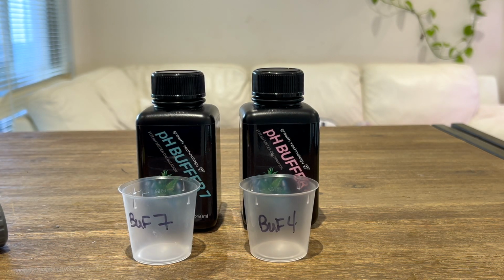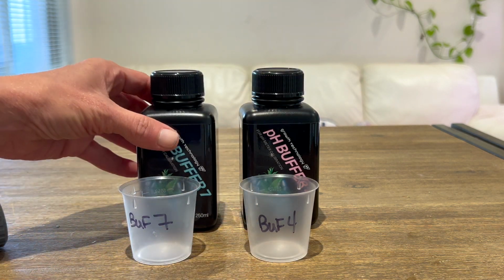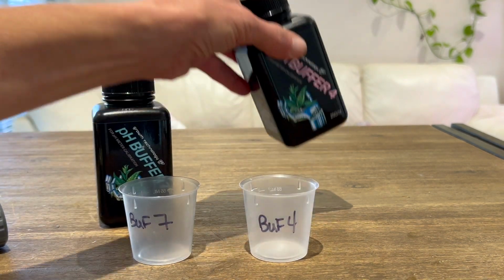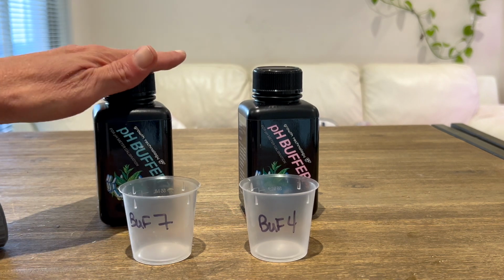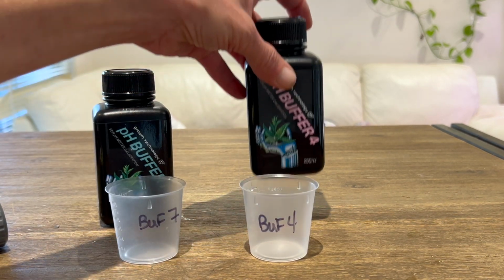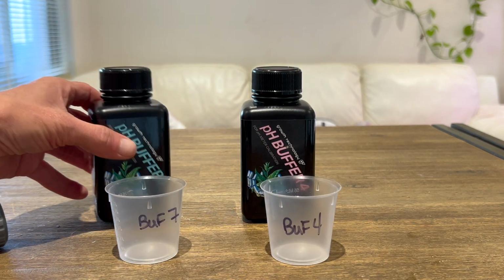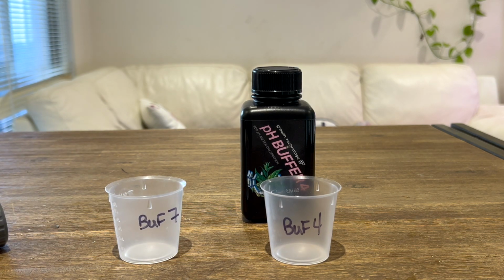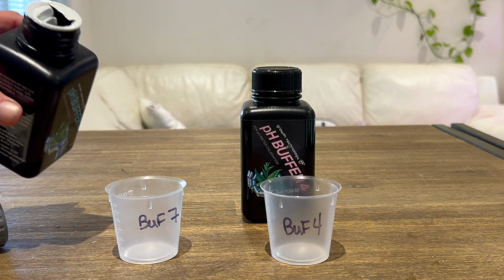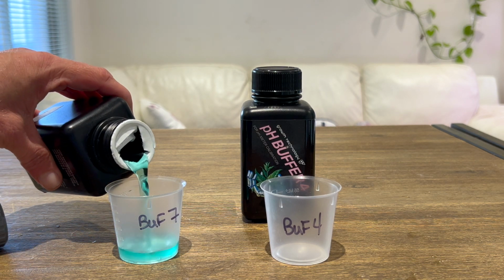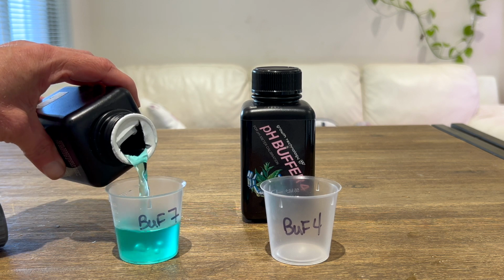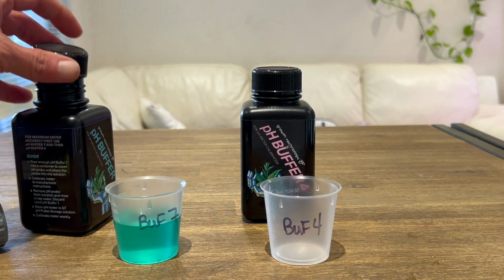So again, never the two shall meet. This will never go there. This will never go here. We're only going to put buffer 7 in buff 7 and buffer 4 in buff 4. Why? Because we don't want to cross-contaminate. When you're dealing with pHs, you do not want to cross-contaminate. So I'm just going to pour enough of this buff 7 in here to cover the probe height.